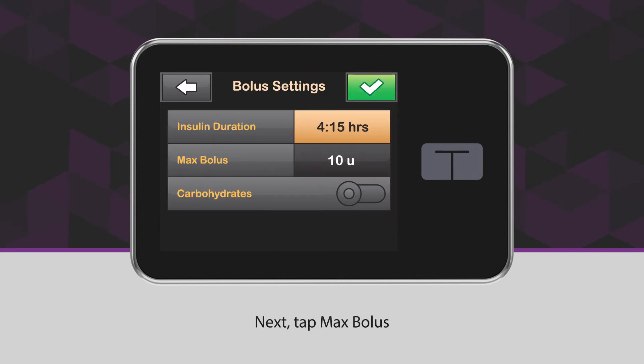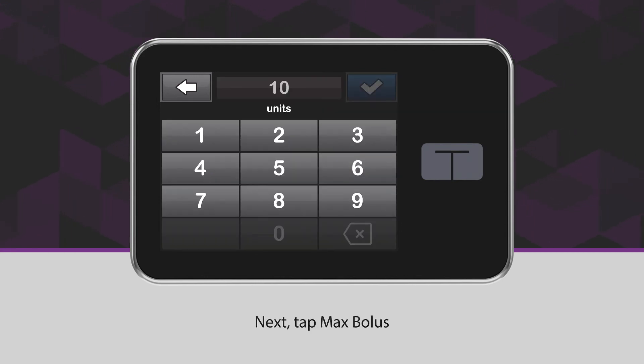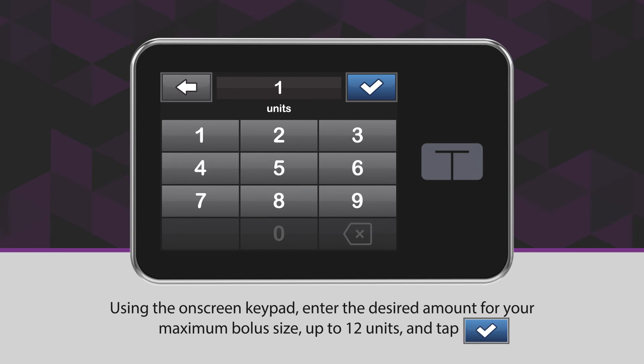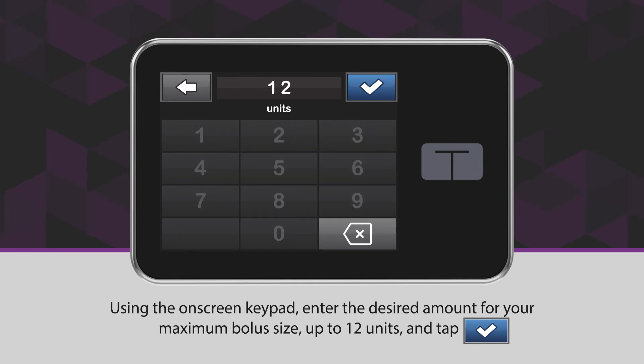Next, tap Max Bolus. Using the on-screen keypad, enter the desired amount for your maximum bolus size, up to 12 units, and tap the blue checkmark icon.